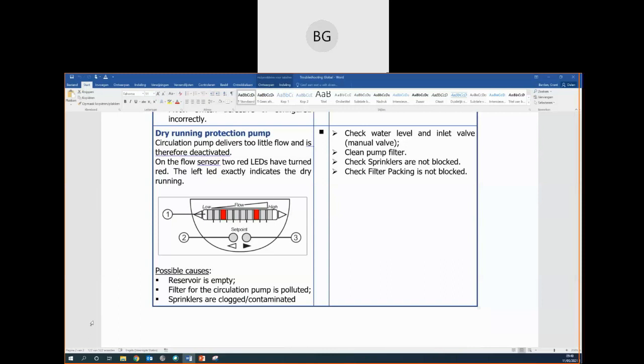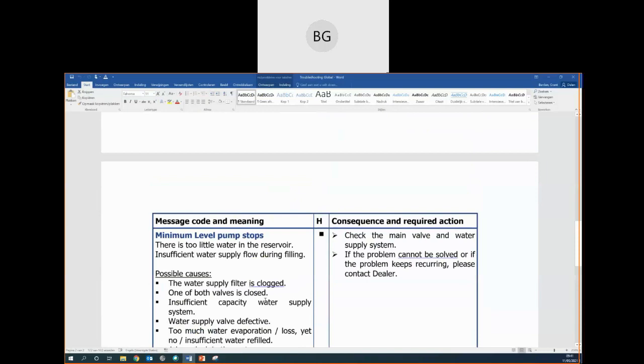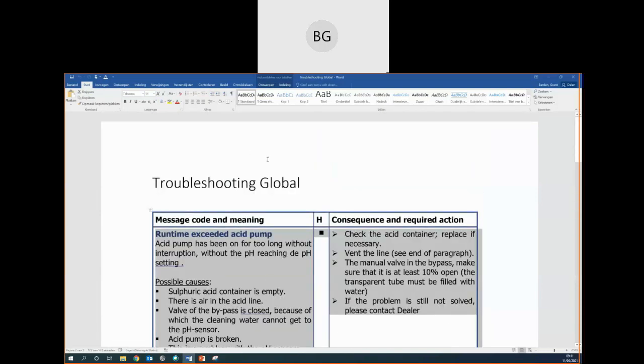So at technician level, we could have that cleaned. Otherwise, at user level, check the water level and the inlet valve, the manual valve. Check the pump filter. Check the sprinklers are not blocked, and check the filter packing is not blocked. This will also be available in print in the unit when it's supplied. So if there are any questions on that, I'll take those now.